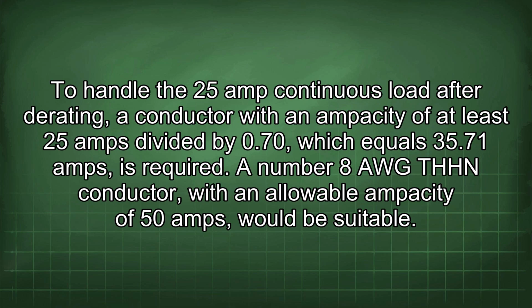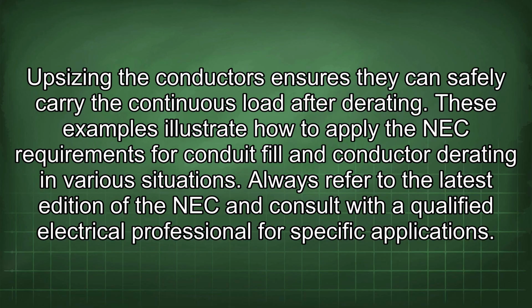To handle the 25 amp continuous load after derating, a conductor with an ampacity of at least 25 amps divided by 0.70, which equals 35.71 amps, is required. A number 8 AWG THHN conductor with an allowable ampacity of 50 amps would be suitable. Upsizing the conductors ensures they can safely carry the continuous load after derating.